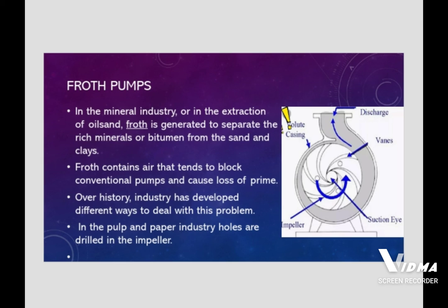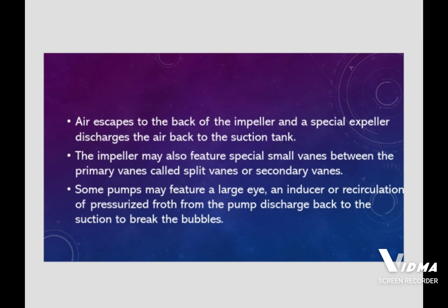Froth pumps are used in the mineral industry or in the extraction of oil sands. Froth is generated to separate the rich minerals or bitumen from the sand, but froth contains air that tends to block conventional pumps and cause loss of prime. Over time, industry has developed different ways to deal with this problem. In the pulp and paper industry, holes are drilled in the impeller. Air is kept to the back of the impeller, and a special expeller discharges the air back to the suction tank. The impeller may also feature special small vanes between the primary vanes, called split vanes or secondary vanes. Some pumps may feature a large eye, an inducer, or recirculation of pressurized flow from the pump discharge back to the suction to break the bubbles.